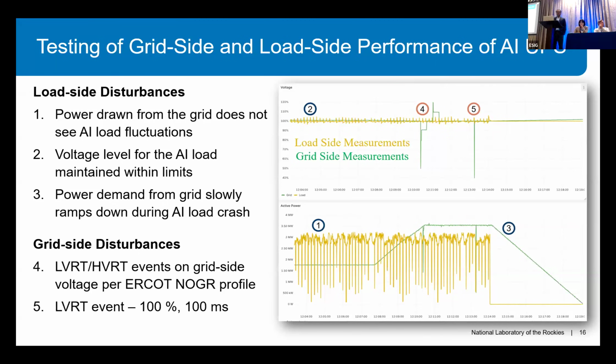Mike from On Energy will talk more about this UPS later today, but the main goal of this UPS is to use battery energy storage to isolate load disturbances from the grid. So the grid doesn't see any AI load fluctuations or load crash, and the load doesn't see any disturbance on the grid. If there is a low voltage blip on the grid, the load voltage remains constant, and that can be demonstrated using some of these measurements here.